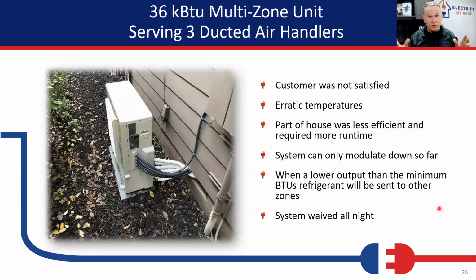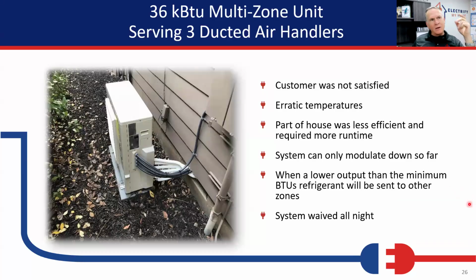$35,000 later, however much it was. This is back in 2018, so it was probably about that much money. That would be like a $50,000 job now, probably. The system just couldn't maintain. So it was doing all kinds of weird stuff. And we had to use the multi-zone mini split ducted heads, the low static versions. And those require the fans to run continuously to sample the air because they use the thermistor in the air handler. So that means the fans are running just a tiny bit all the time.